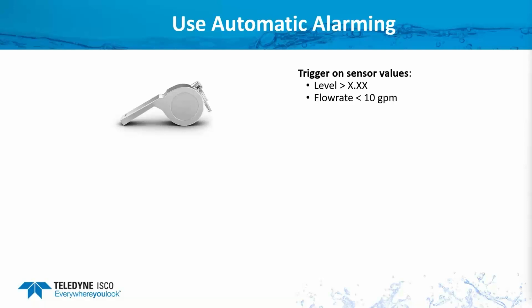And so you can either have your instrument, if you have a modem on there, send you a text message to let you know that there's a surcharge condition going on, or you can have the Cipher software send a text message or an email letting you know what's going on. Other parameters you can choose is if your flow rates are less than a certain value, or the signal strength is lower.